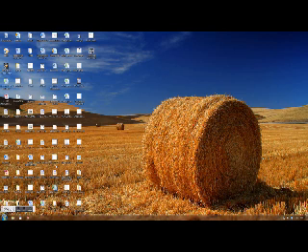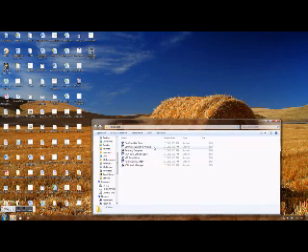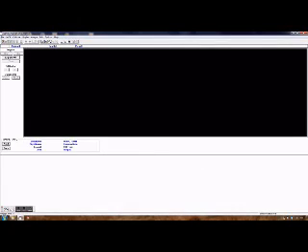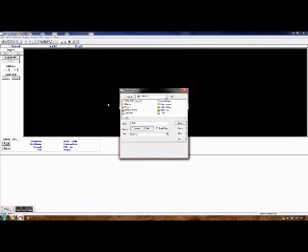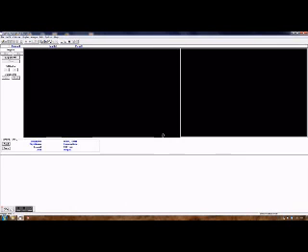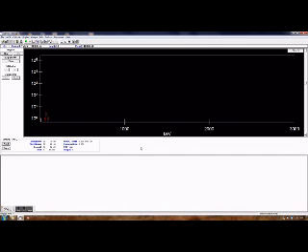Our first step on the computer is to find the Genie 2000 folder and open it. In here we're going to open the Gamma Acquisition and Analysis. Now we come up to File, Open Data Source, select Detector, select the detector, and then click Open. This tells the Genie 2000 software what kind of detector is hooked up, so it will perform calculations accordingly.